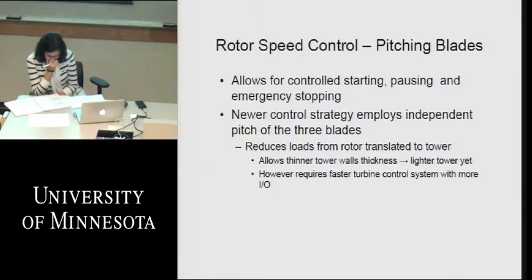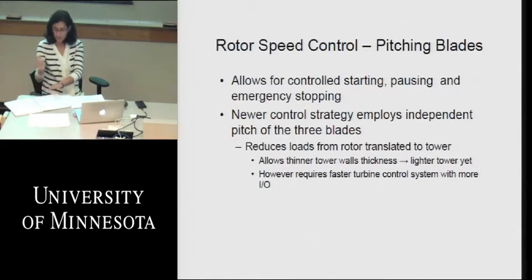Pitching the blades also allows for controlled starting, pausing, and emergency stopping in a wind turbine. We have a hydraulic brake, essentially a disc brake, on the main drive shaft, but if we used that to stop the machine all the time, we'd wear out those pads very quickly. But we can effectively stop the machine just by pitching out from a zero angle during normal operation. It hits the blades 90 degrees to the apparent wind, and the turbine will stop within 2 or 3 revolutions. It's really a remarkable thing to see. It just powers down and stops. We actually use it for starting the machine. We use a little bit of aggressive pitch to get the machine started in low wind, and then we move it to about a 0 datum angle on the pitch when we're in normal power operation, and when we reach rated conditions, we're spilling a little wind so we don't overdrive the design of the machine.